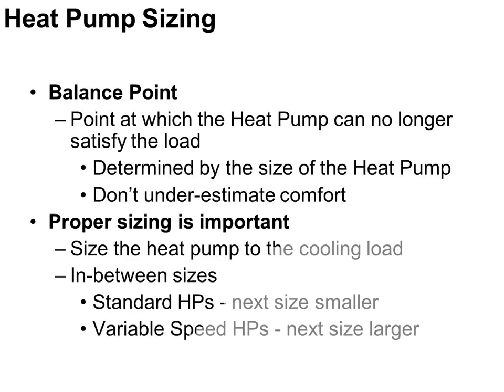When I have a variable speed piece of equipment, I can upsize it a little bit. Now, I don't want to get crazy. I don't want to put the 8-ton unit in on the 3-ton load and expect it to ramp properly, right? But instead of rounding from 38,000 BTUs down to the 3-ton, I can round it up to a 4-ton, right? And I have the ability to vary the capacity of that system, so I could still get really good dehumidification, even better than a regular system in the summertime.